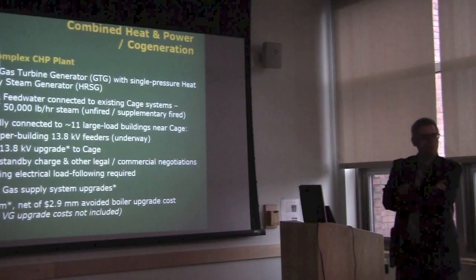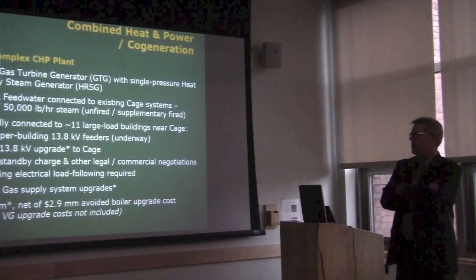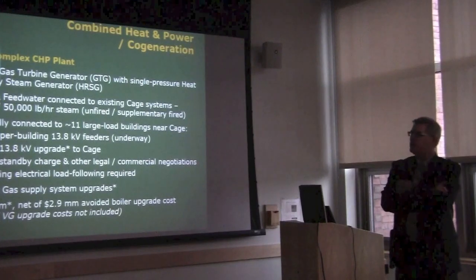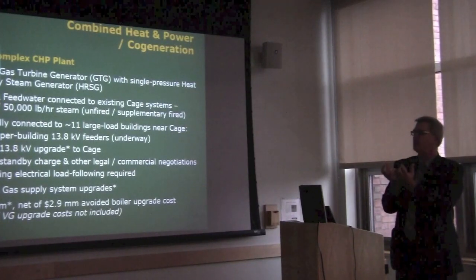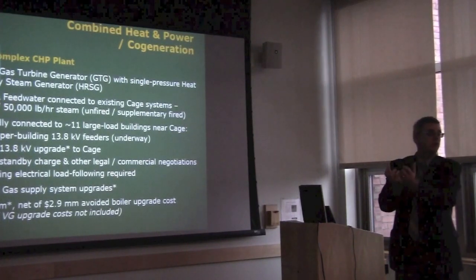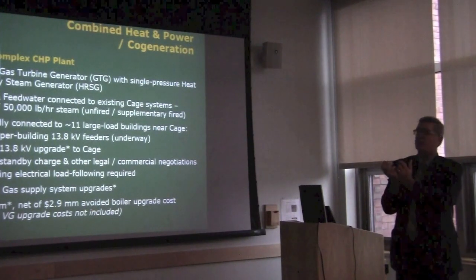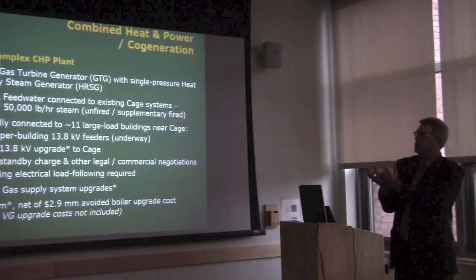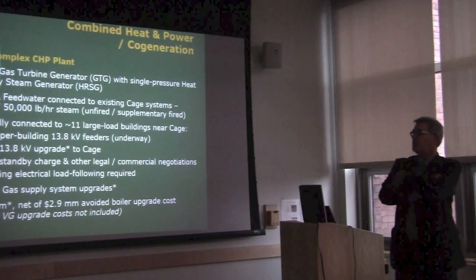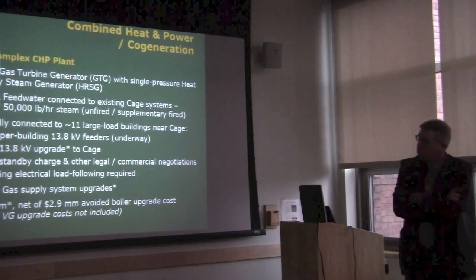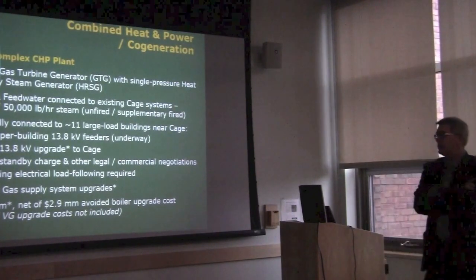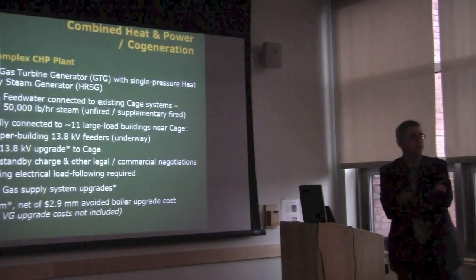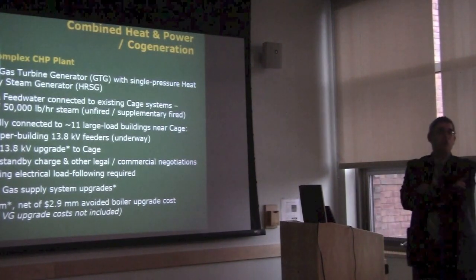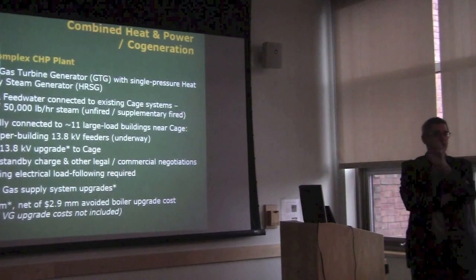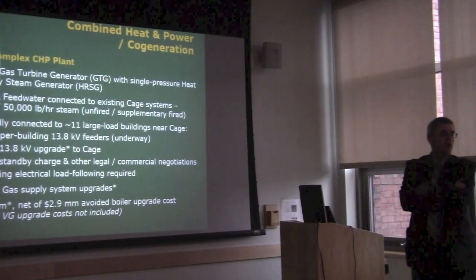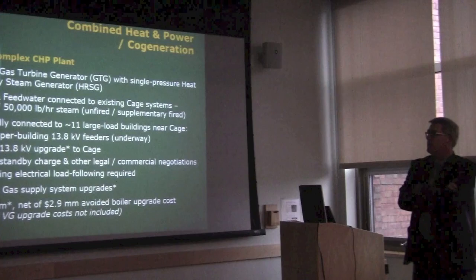We'd be making about 19,000 pounds per hour of steam in the unfired condition. If you take those hot exhaust gases leaving the gas turbine and add additional fuel, it raises the temperature dramatically, and you can increase steam production up to around 50,000 pounds per hour. Curiously, there are rarely times where you're under 50,000 pounds per hour based on your current load profile - this is the net steam production out of the Cage complex. So this is a pretty good fit.